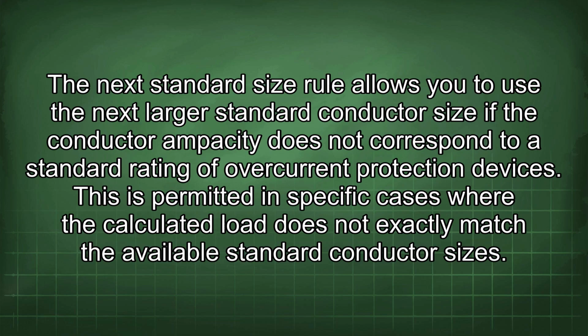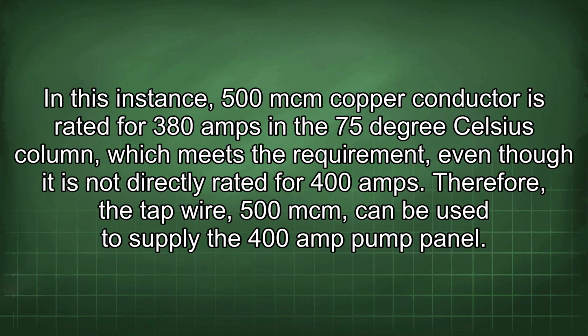The next standard size rule allows you to use the next larger standard conductor size if the conductor ampacity does not correspond to a standard rating of overcurrent protection devices. This is permitted in specific cases where the calculated load does not exactly match the available standard conductor sizes. In this instance, 500 MCM copper conductor is rated for 380 amps in the 75 degrees Celsius column, which meets the requirement, even though it is not directly rated for 400 amps. Therefore, the tap wire 500 MCM can be used to supply the 400 amp pump panel.